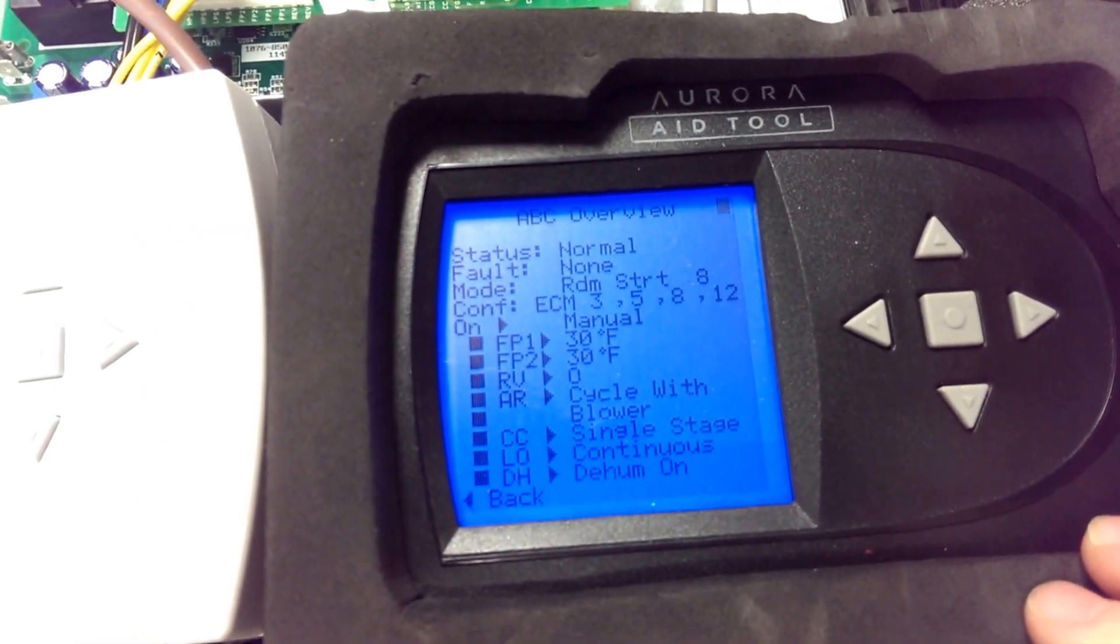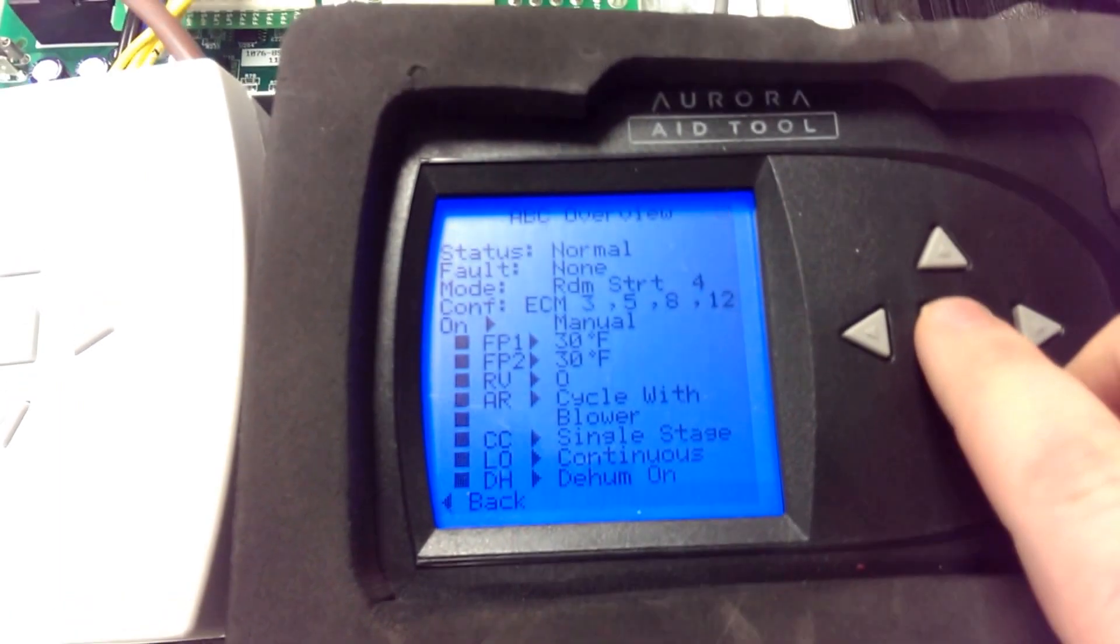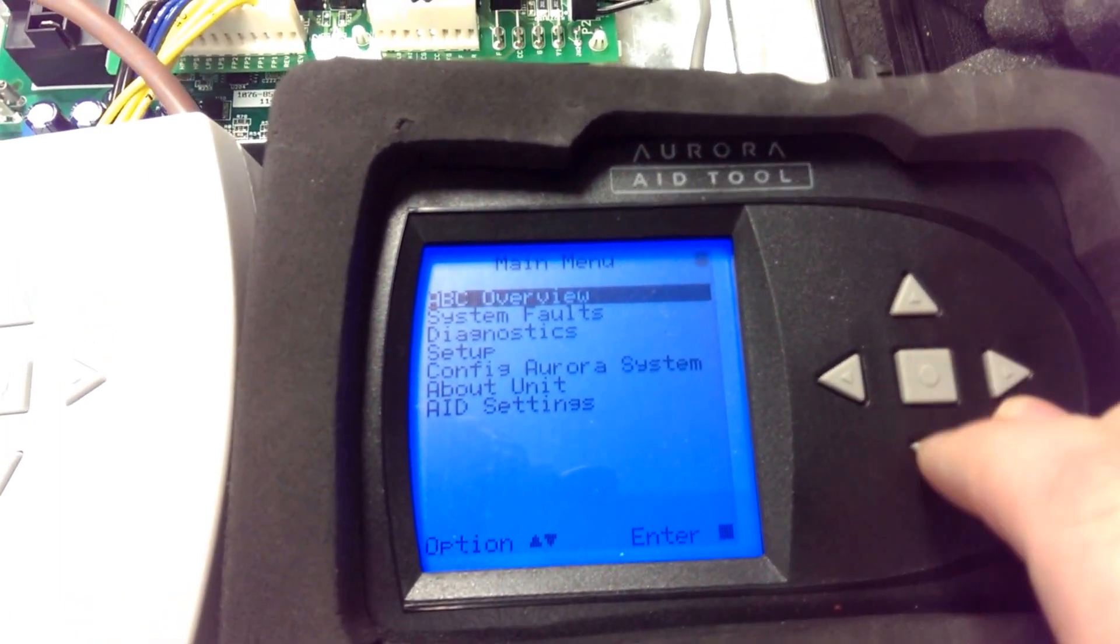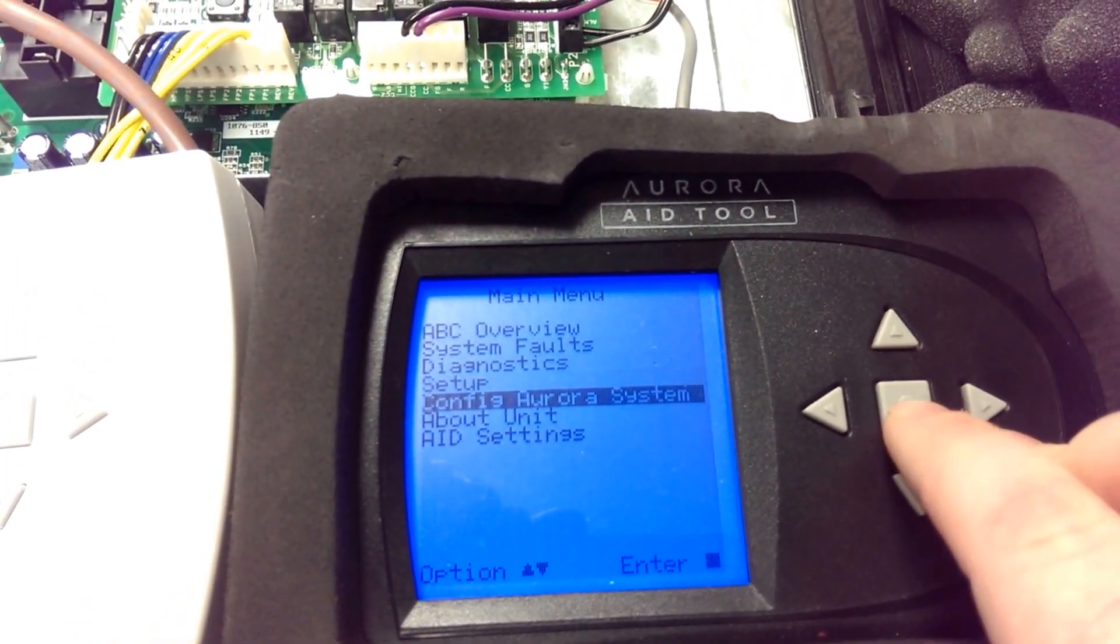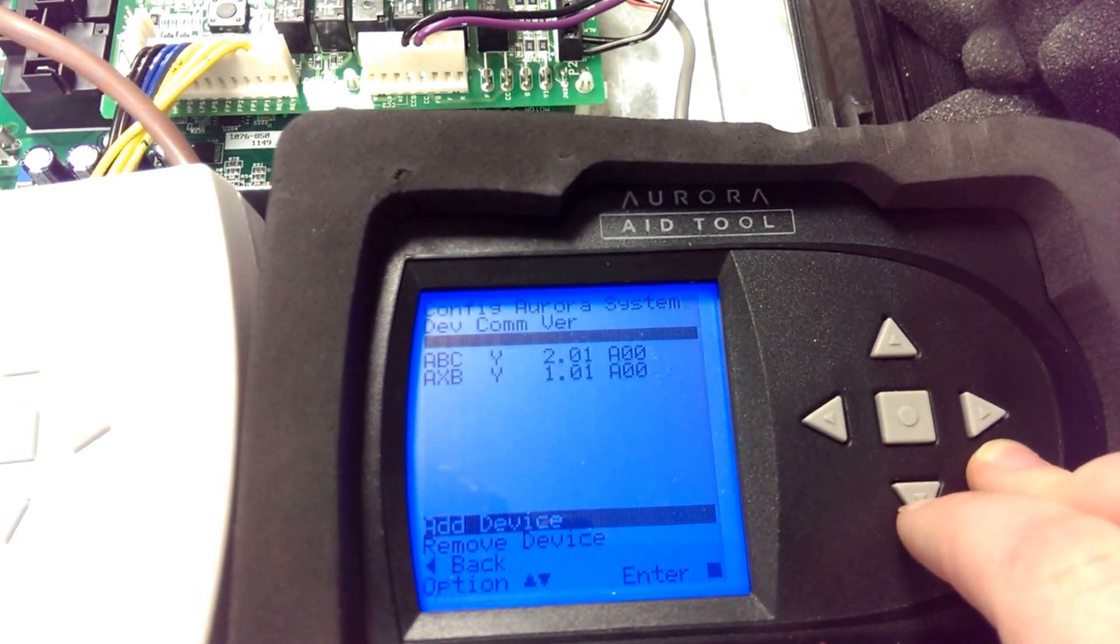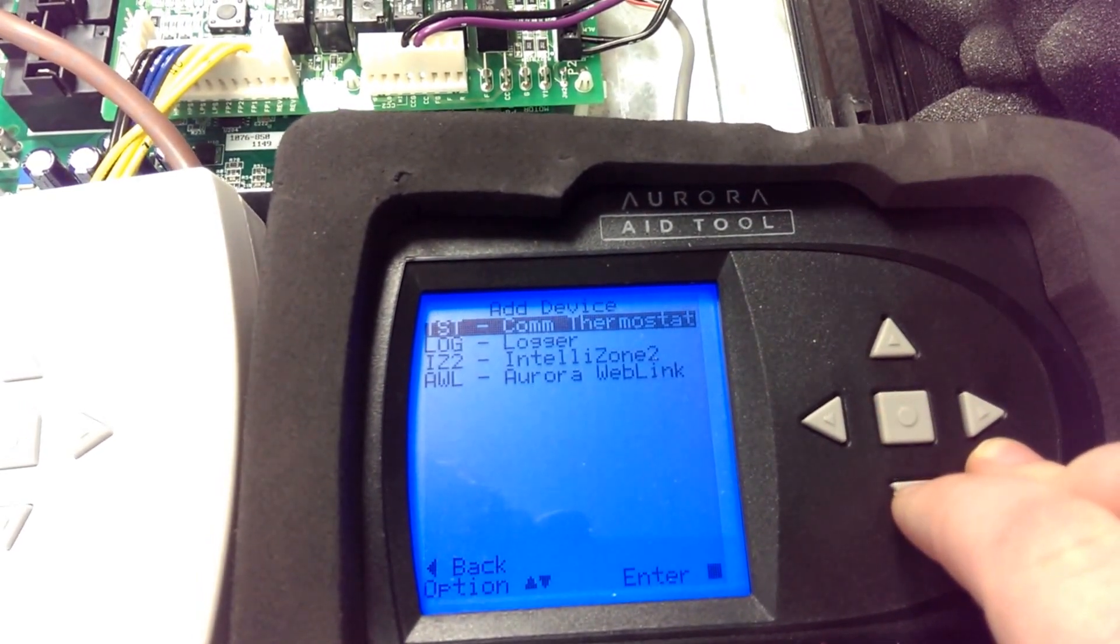With our AID tool, which is plugged in right here on the board, we take our AID tool and press the first button once. We go into Config Aurora System, add device, and add a communicating thermostat.